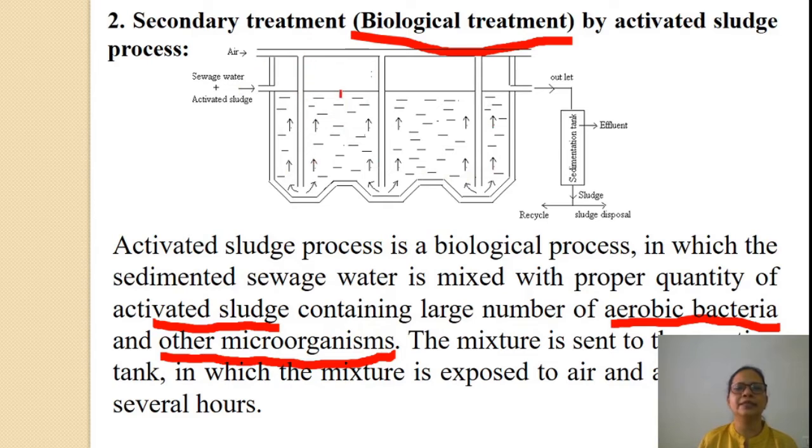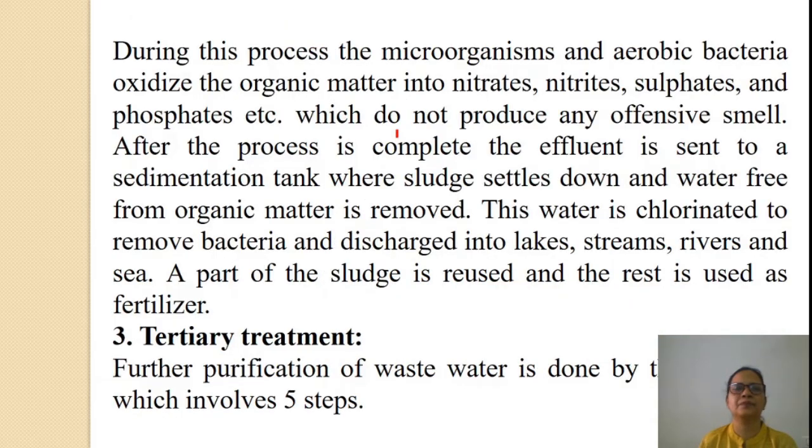You can see here air is passed through these pipes and agitated, stirred for several hours. The pressure of the air makes the mixture agitate and this process is continued for several hours. During this process, the microorganisms and aerobic bacteria oxidize the organic matter into nitrates, nitrites, sulfates and phosphates, which do not produce any offensive smell.